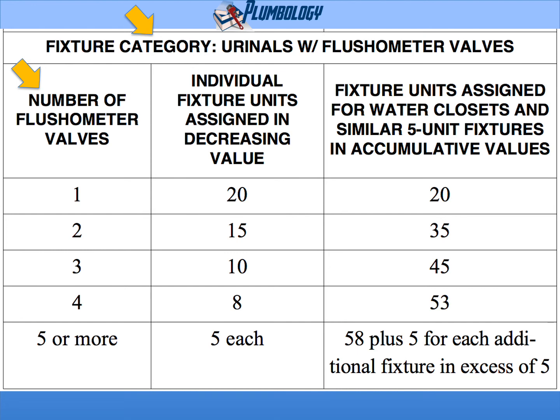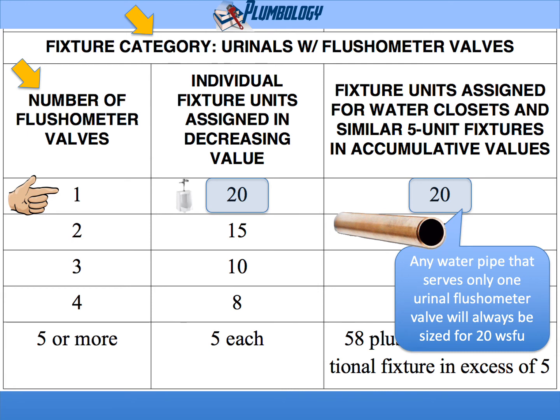The bottom half of Table 610.10 is for the category of urinals with flushometer valves. The left-hand column is the same: 1, 2, 3, 4, 5 or more. What changes is that the decreasing scale for urinal flushometer valves is different. Instead of 40, 30, 20, 15, 10 like we had for water closets, we're going to have 20, 15, 10, 8, and 5 for the urinals. If you have one urinal flushometer valve, its value is 20 water supply fixture units, and the accumulative value for that branch piping would be 20 fixture units. So any water pipe serving only one urinal flushometer valve will always be sized for 20 water supply fixture units.